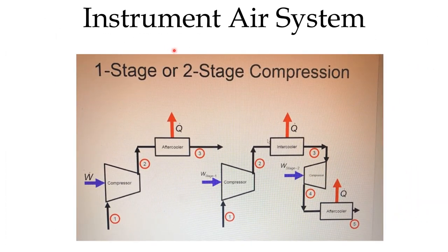Here is the schematic of a single stage and two stage compressor. The single stage compressor has only an aftercooler. The two stage compressor has an intercooler between the first and second stage, and an aftercooler after the second stage, going to the plant air receiver followed by the instrument air dryer.